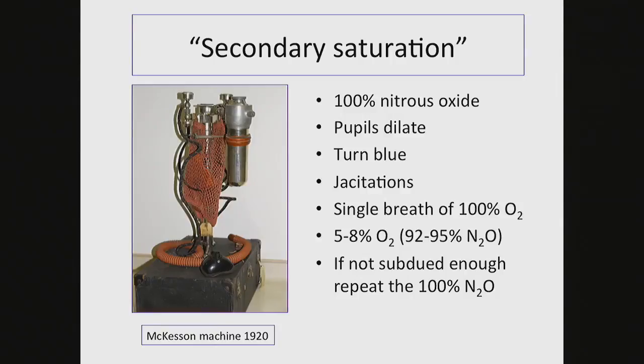It was called the technique of secondary saturation, where patients would be given 100% nitrous oxide until they turned blue, the pupils would dilate, and they would ultimately start fitting. They're called jactitations. At that stage, they would give the patient a single breath of 100% oxygen, and this machine could do it. It could deliver both gases at a high pressure if needed.